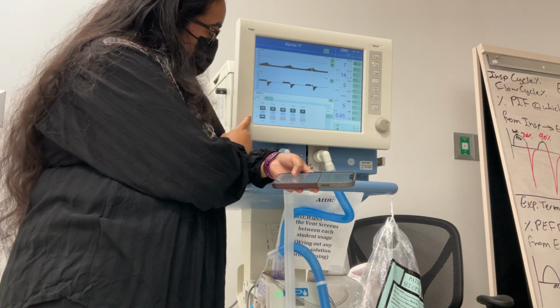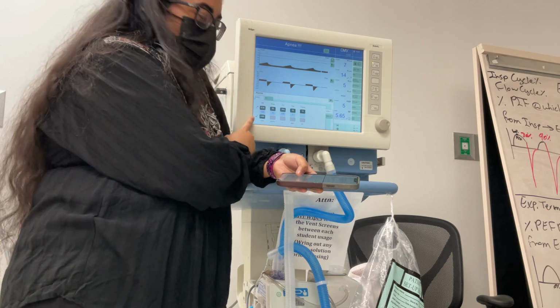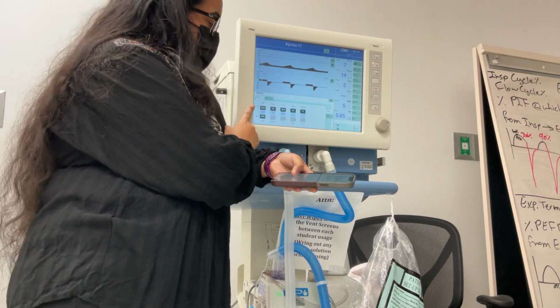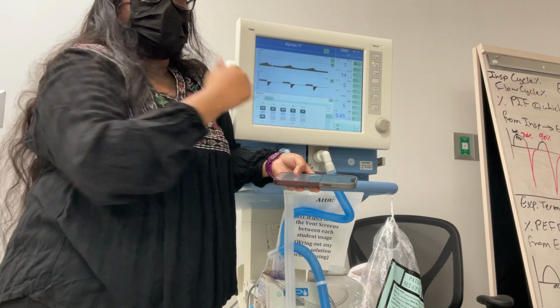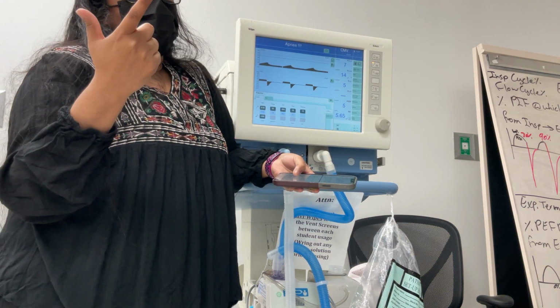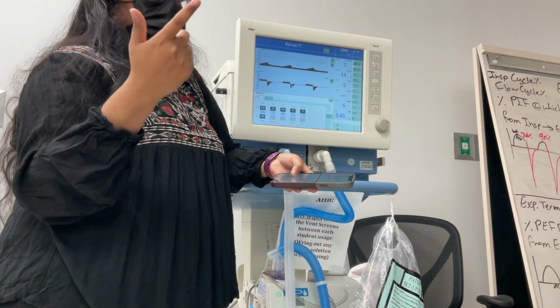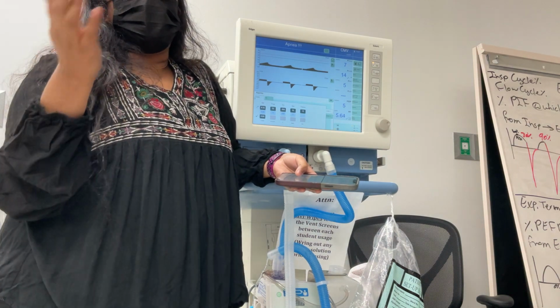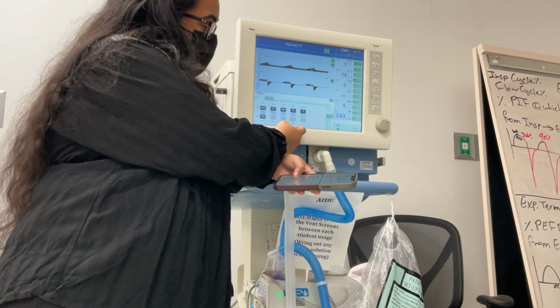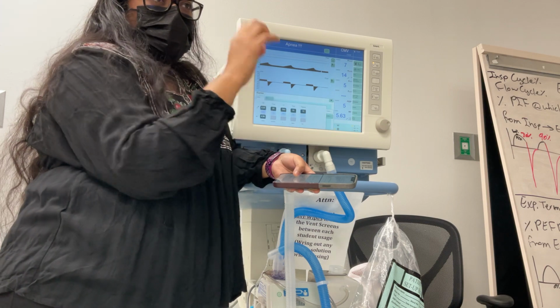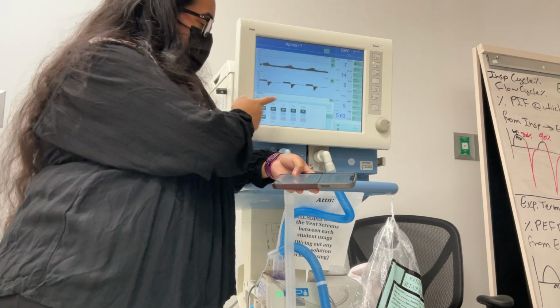You've got your minute ventilation alarm. For the low, you just do 1 below. For high, you can do 2 above, or you can do math: tidal volume times respiratory rate. You'll use your high respiratory rate. You'll set a high respiratory rate, usually at like 25. Use that 25 multiplied by your volume, and you'll have your high alarm.